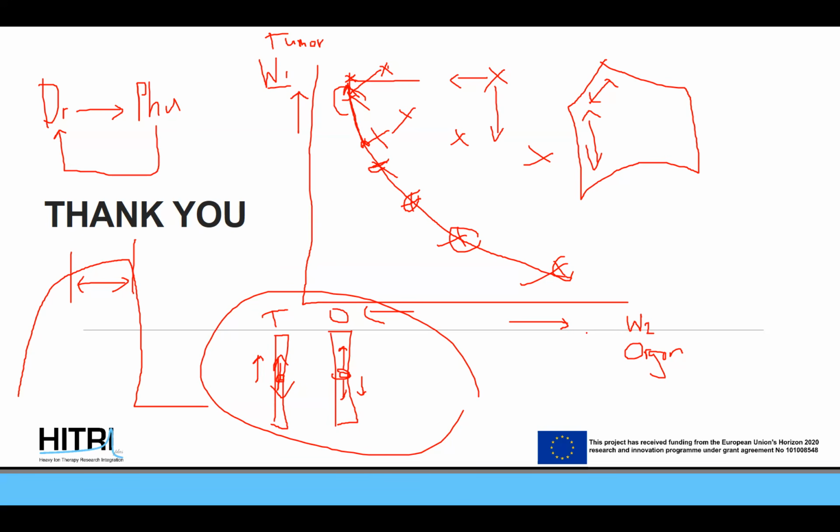As a physicist who has experience in photons and protons, would you say that your planning technique is the same in photons and protons? The optimizer should not be a problem. The big difference is the delivery of the radiation, which is very different. So the delivery becomes a critical component. When you finish the optimizer, you have to deliver it. You have to pass it through a leaf sequencing algorithm for photons, or through a pencil beam scanning algorithm to produce the pencil beam. So the delivery method changes, and it is usually a bit tricky. Okay, great, thank you.